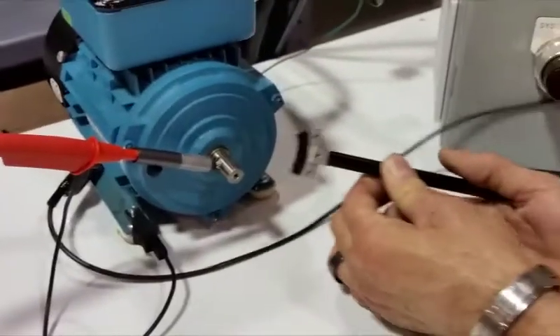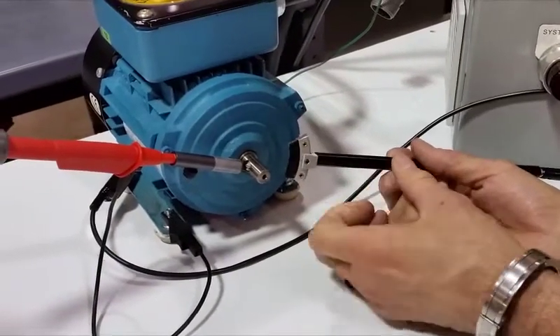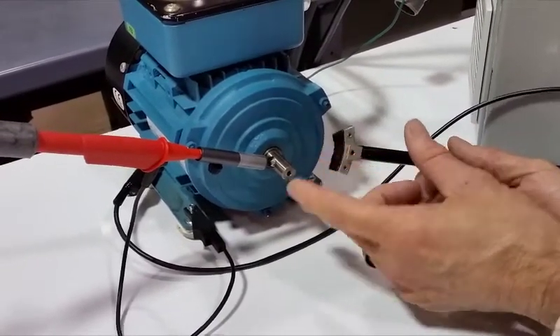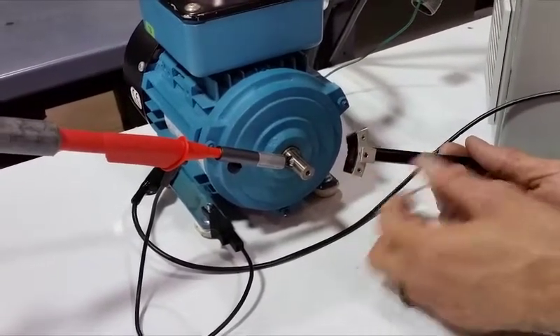This here is an example of a shaft grounding ring. It's cut open to demonstrate the use of them. Normally these rings are installed within the motor. The brushes are touching the shaft and taking the stray currents to ground.